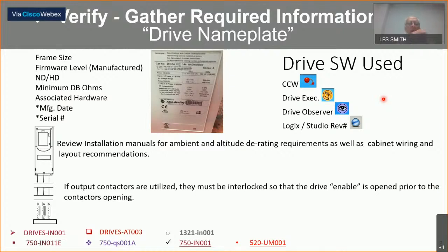And as you see here, I started to look at how to put in a drive, and the quadruple diamond up there in the upper left says that this is the quick start, 750 QS. It's a very good book for putting in 750 drives. It has programming examples, it has wiring examples on a much shorter string of information, easier to read and specific to startups.